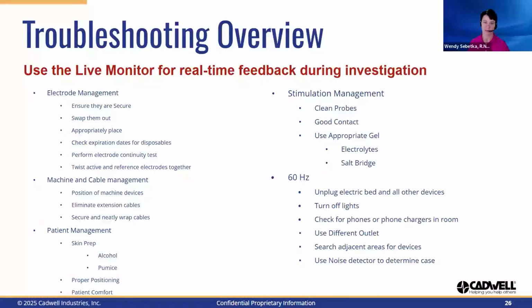Patient management techniques include skin preparation, proper patient position, and ensuring the patient is relaxed, which will improve the outcomes of the study. Stimulation management should include making sure stim probes are clean and free of dried up gel. Applying firm, steady pressure to the patient will not only improve stim artifact, but is much more comfortable for the patient. When using conductive gel, use caution not to use too much, which can create a salt bridge. Troubleshooting of 60 Hz interference can be difficult, but unplugging and eliminating unnecessary devices or swapping power outlets one at a time can help locate the source. If further investigation is needed, reviewing adjacent areas and using a noise detect probe may be necessary. The use of the 60 Hz filter is also available as a last resort.